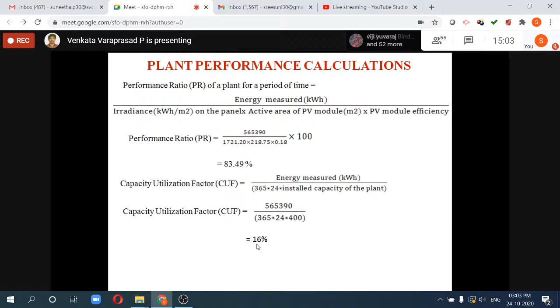Plant utilization factor is the energy measured divided by 365 days into 24 hours times the installed capacity of the plant. So here the installed capacity is 400 kilowatt, so the plant utilization factor is 16%. Next one, day-wise generation, radiation, and performance ratio.